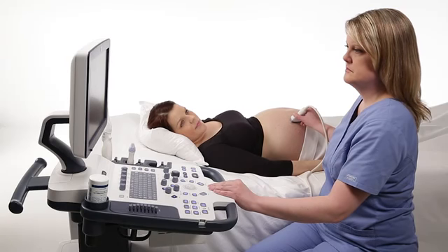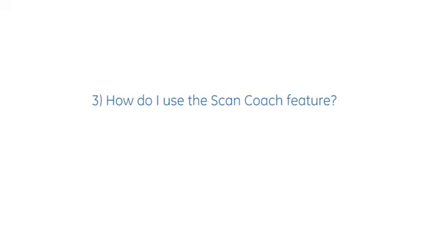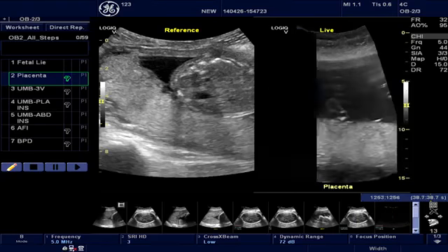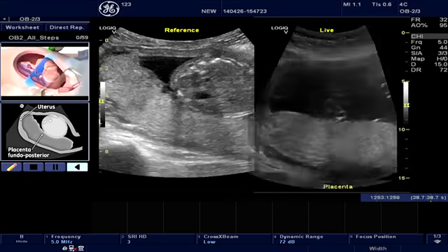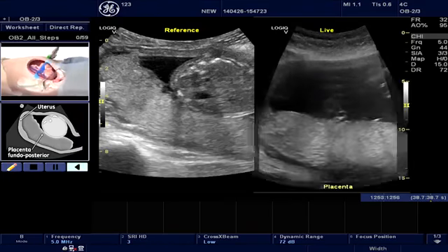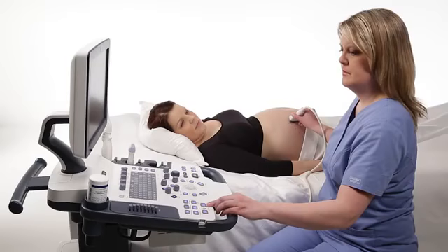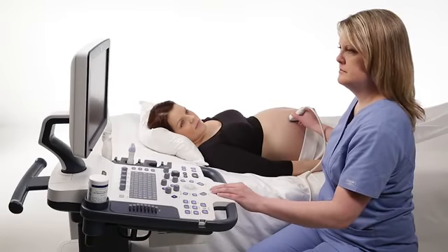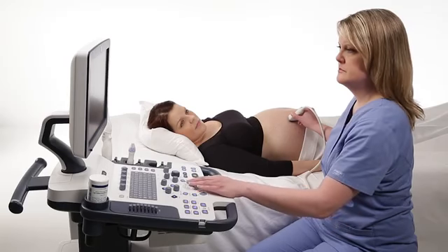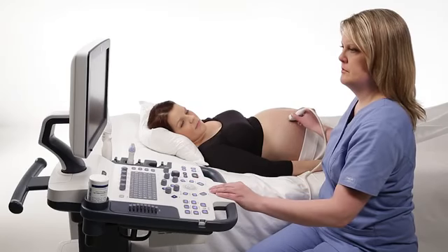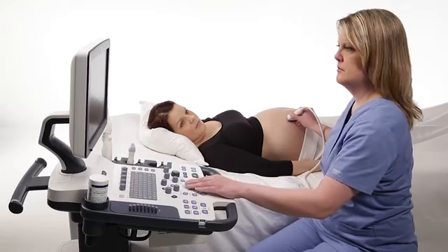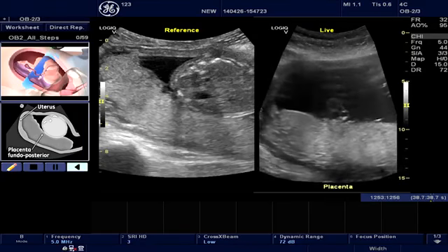Let us now proceed to show you how the Scan Coach feature works. Scan Coach is a contextual reference tool — it allows you to quickly refer to additional information during a specific step or steps in a protocol when you desire. This makes it possible for you to use Scan Coach even while live scanning. Scan Coach leverages the built-in examination script of Scan Assistant and overlays it with reference information on scan plane acquisition and anatomical structures. Scan Coach content can be displayed on demand by the user to quickly refresh some imaging information, which may help some users to acquire a scan plane.